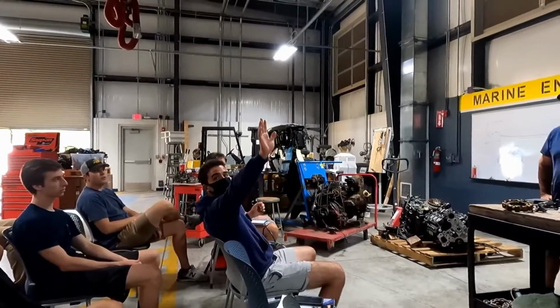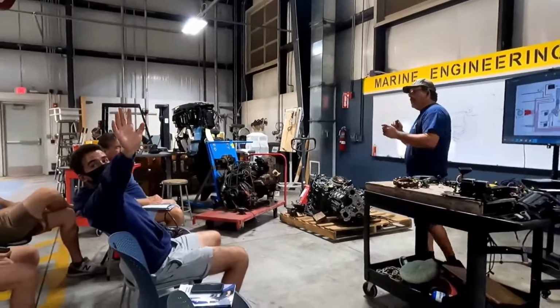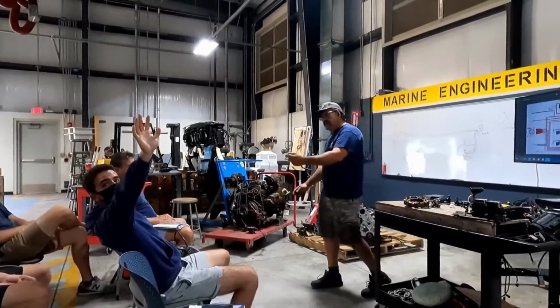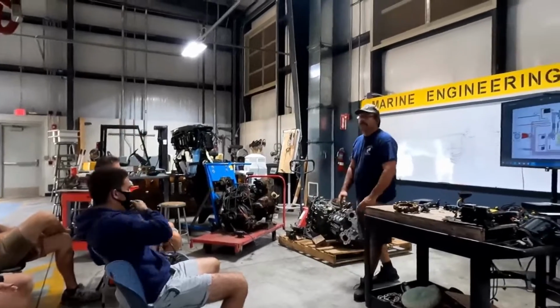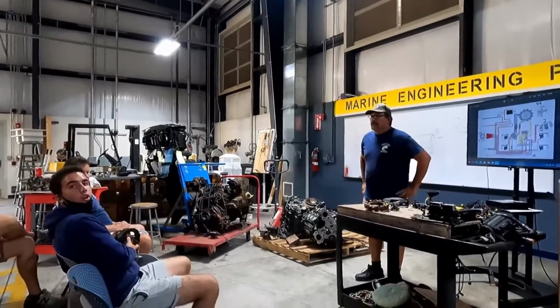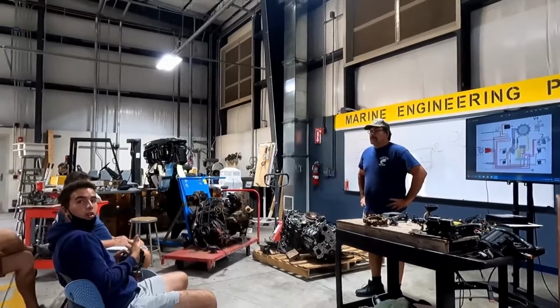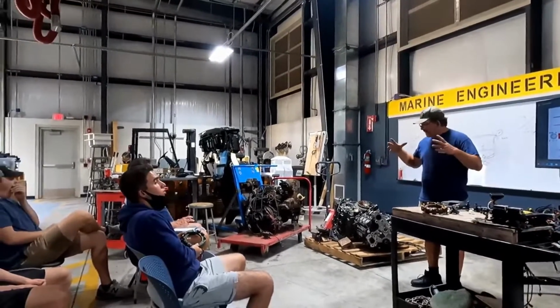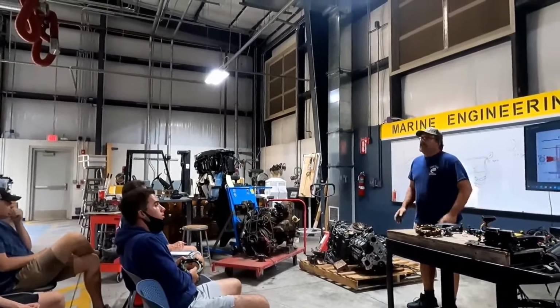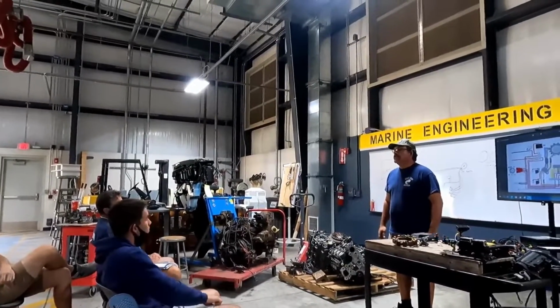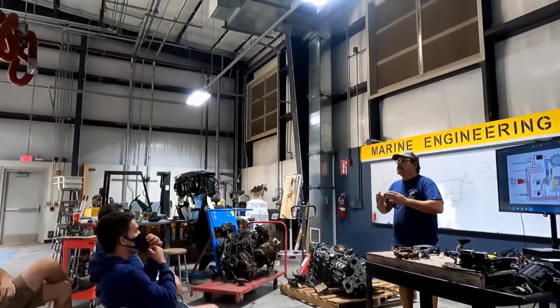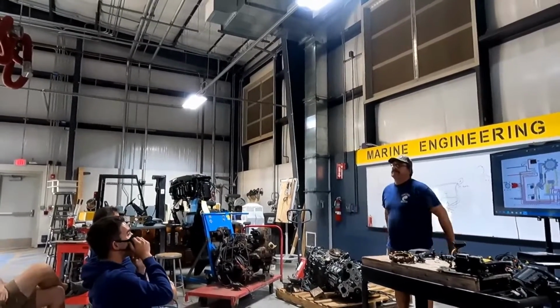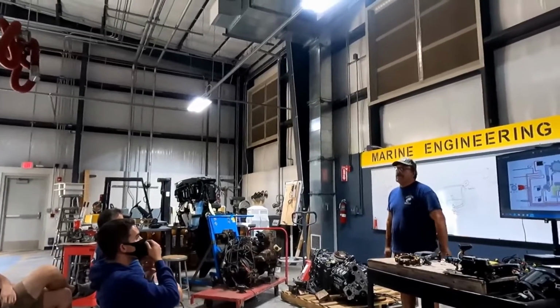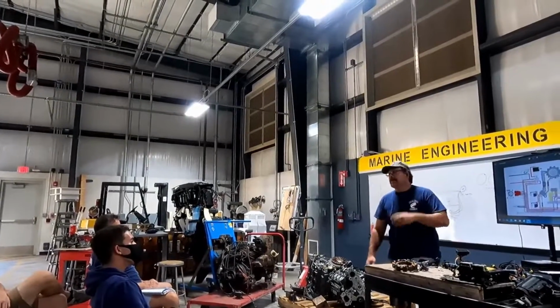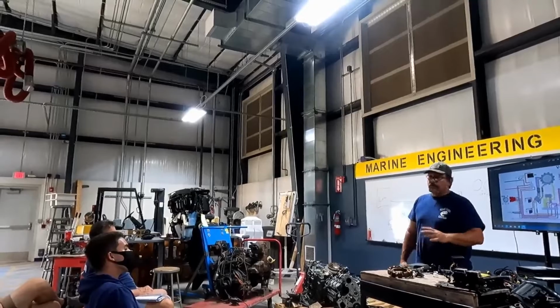What about using a mirror to inspect? You can use a mirror, or you can use one of those borescopes - go underneath the flywheel and look at it. Do that. Since they're like glued in, what would cause that? Too much heat? No, it's because it's a glue, an epoxy, on a steel flywheel. And what happens to steel when it corrodes? It oxidizes and swells, and the epoxy comes off. Some, you can glue the magnets back on - you have to clean it, do a 2-part epoxy, they sell it - and then some magnets just need to be replaced.